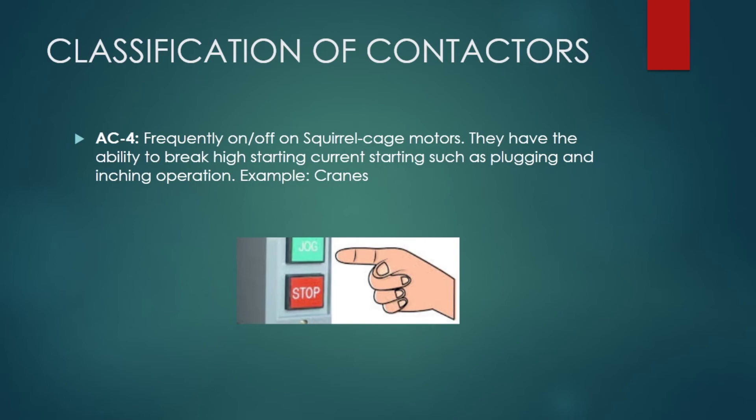The AC4 contactor is widely used where the squirrel cage motor is frequently switched on and off, or very fast switching is performed by the operator. The main feature of the AC4 contactor is its ability to break high starting current, such as in plugging and inching operations. They are widely used in the operation of heavy duty cranes.